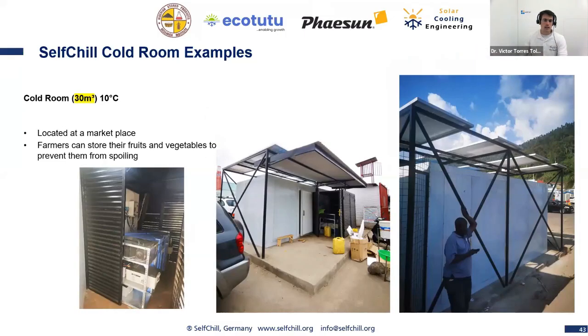Okay, so another sample, another cold room at a marketplace, 30 cubic meters, 10 degrees. You see here where the water chiller is. The thermal storage is in a separate space, outside of the cold room. And then we have a roof and the PV panels on top, and the cold room. Very nice systems. Sandwich panels can also be directly in the rain, so there's not a problem because they are waterproof, inside and outside. So this is quite easy to build.